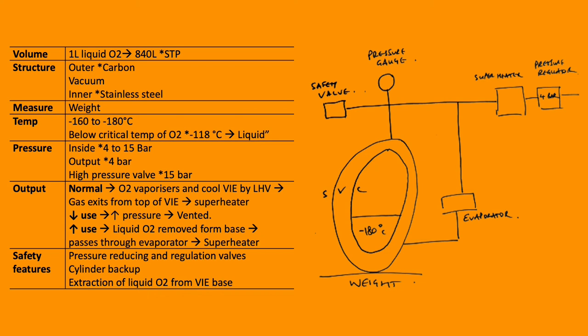And finally, under high demand, rapid vaporisation of oxygen drops the temperature in the chamber. So liquid oxygen enters the evaporator which is a large surface area and uses ambient temperature to allow rapid vaporisation to a gaseous oxygen state.